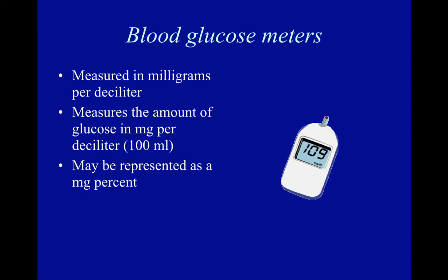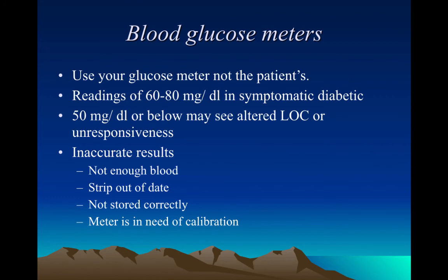Some glucometers are used just for an individual. They're not designed to be used by multiple different patients. So that's one thing you need to make sure of: that the glucometers your service is using are actually for multi-patient use. Some common sense pieces here: always use your glucometer, not the patient's glucometer, with the idea that yours is kept up to manufacturer's recommendations, and that it's user ready for every patient every time.